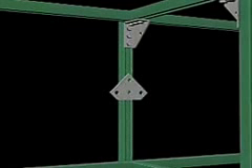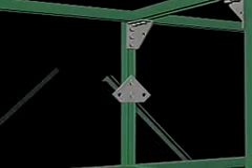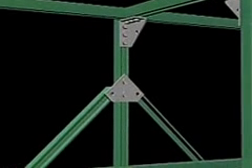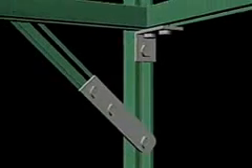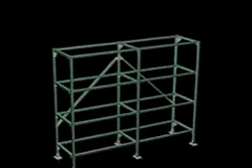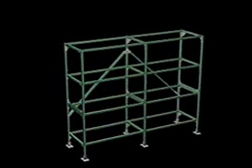Next, attach a brace fitting to the top portion of the center stanchions. Connect 2 5-foot 2 3/4-inch lengths of channel to this connector. These are the braces. Attach the braces to the lower portion of the end stanchions with the P2324 swivel plates. Slide in the plywood and the storage rack is complete. Slide the plywood out and you have a frame that is ready made to support pipe, conduit, cable, or cable tray.